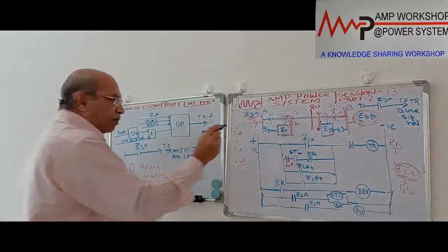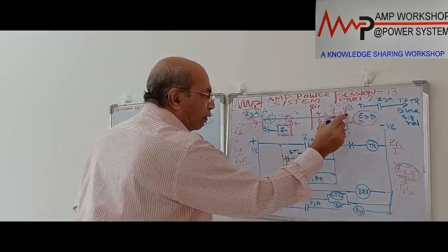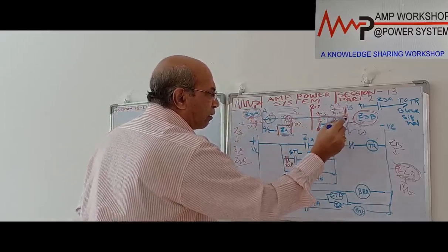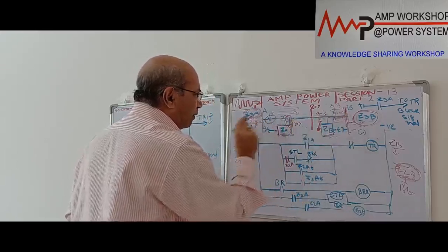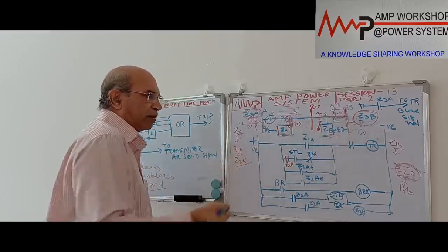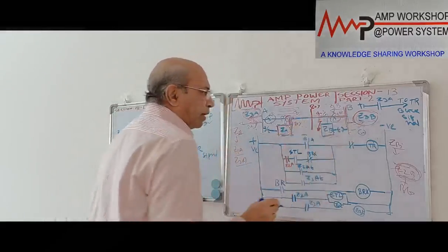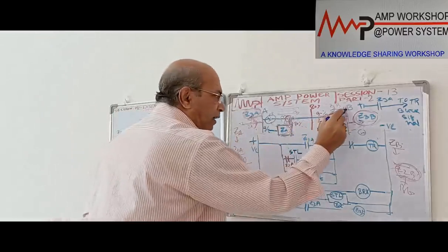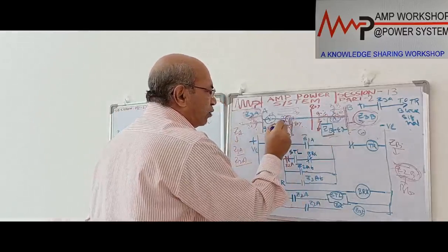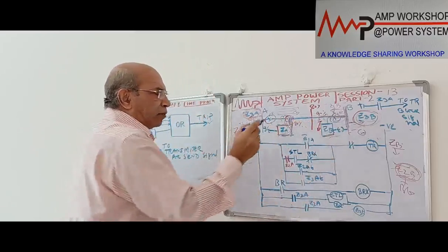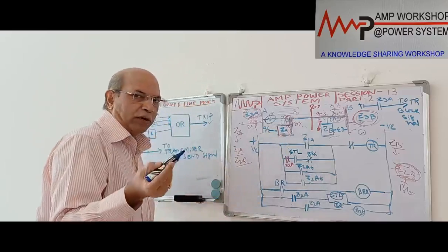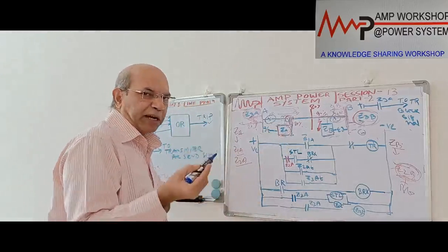Now this breaker is off, but there is still a generator connected over here, so it is still feeding the fault. So the fault feeding at this end is stopped, but at the other end it is not stopped, so we have to trip that breaker. From the other end, this fault is within the end zone, that is, after 80%, an end zone fault. An end zone fault is to be cleared in the zone 1 timing. That is our intention. That's why we will expedite the tripping.